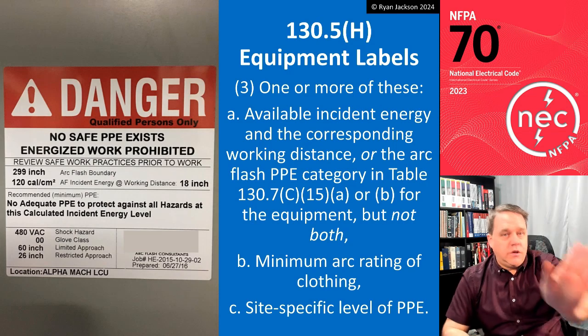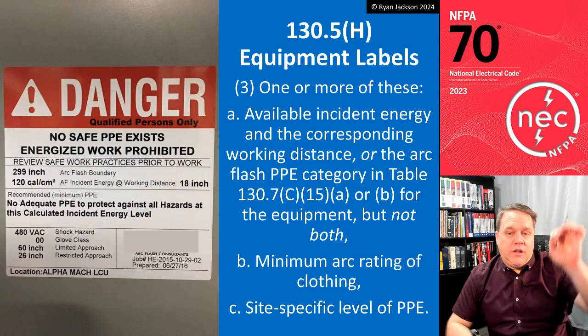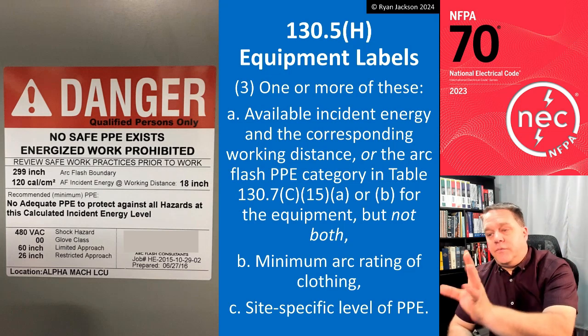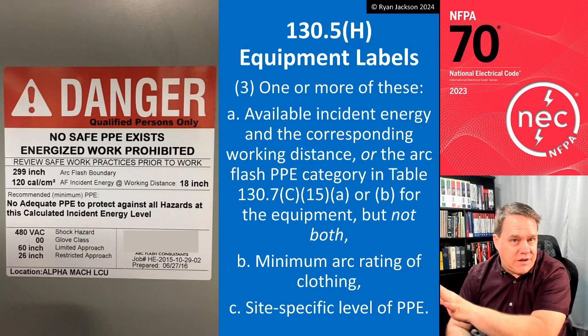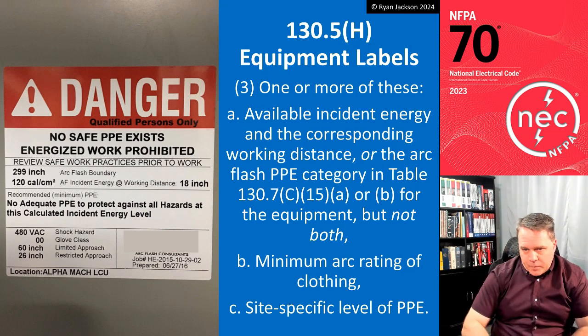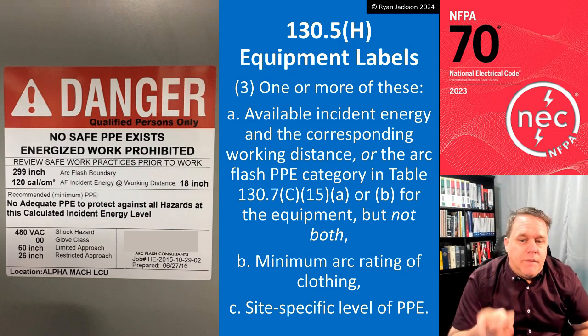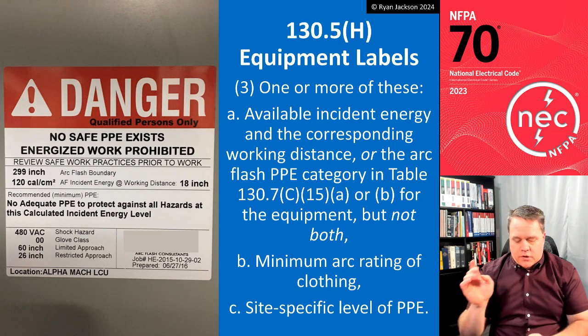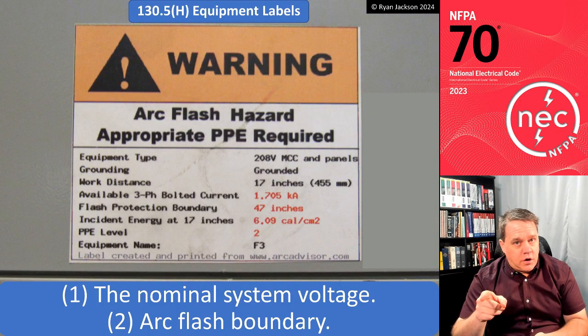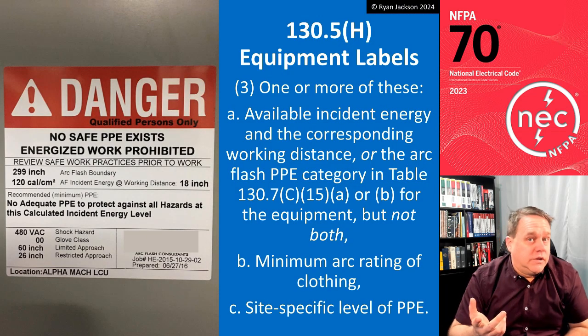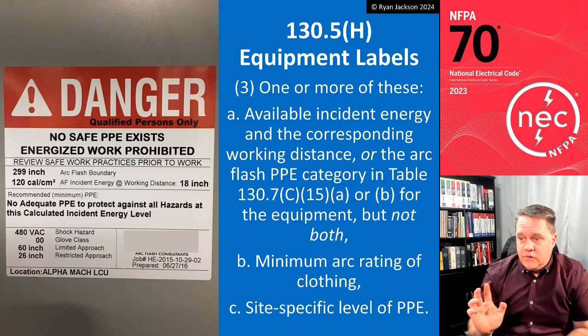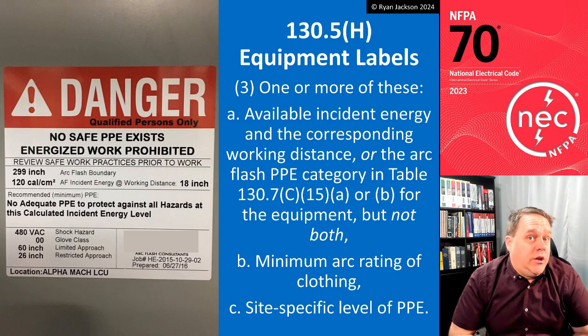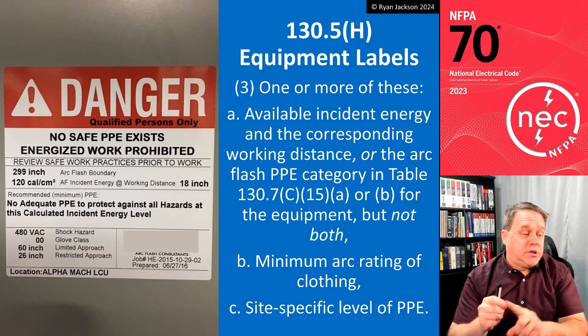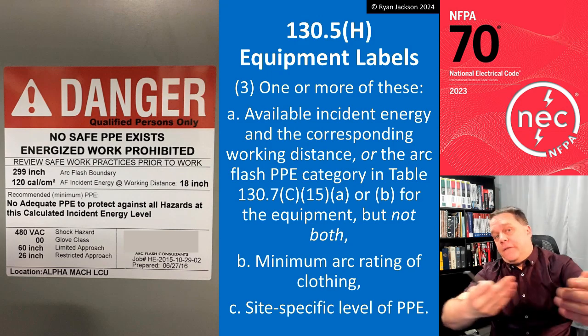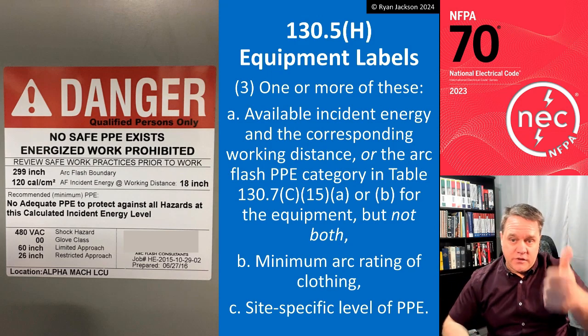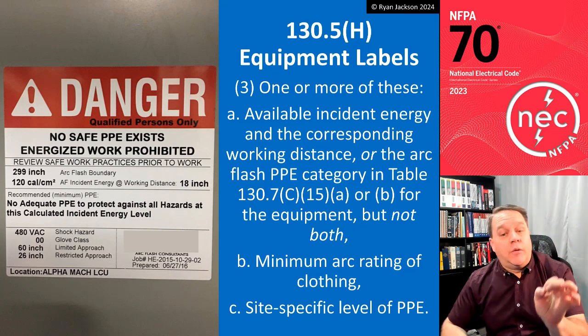You're either going to do the calculation method or you're going to do the table method. All right. If you do the calculation, tell me the incident energy. If you do the table method, then you're going to tell me the arc flash PPE category, category 1, category 2, etc. Or you could just tell me the minimum arc rating of clothing. All right, so you go back, tell me the voltage, tell me the arc flash boundary, and tell me the arc rating of clothing, right? So you know the boundary, 47 inches. If you just tell me, hey, wear 35 calorie equipment, all right, I know what to do. I know my shock protection, right? So I know what category my gloves need to be, and I know how far away the arc flash boundary is, and I know what to wear. So tell me the incident energy, or the category method, or the minimum arc rating of clothing.